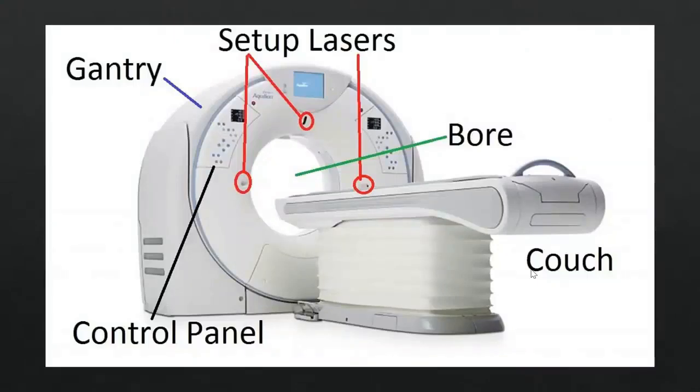We will quickly go through the slides that are available. Of course, we know the main shape of the CT system. I have a gantry like this, and I have a table or couch, and I have the bore where the patient enters. The gantry, of course, contains the X-ray imaging tube, and on the opposite side, I have the detector. The shape you see here is the laser that I use for alignment. I have a laser that is positioned in front of the patient, and there is one lateral laser.